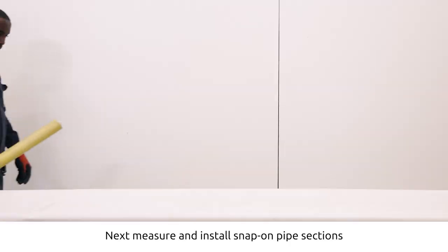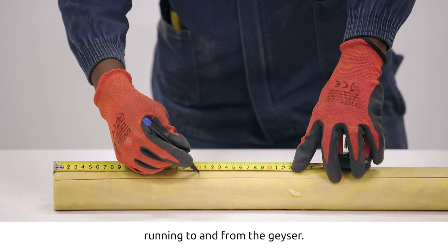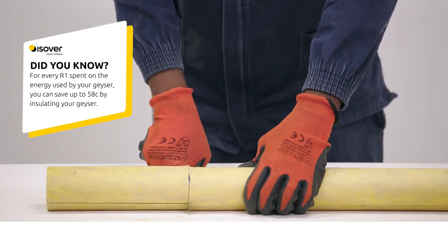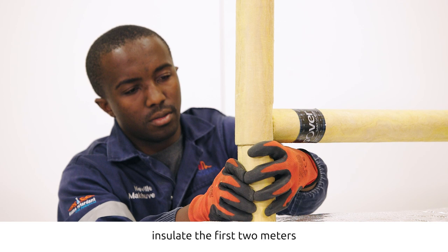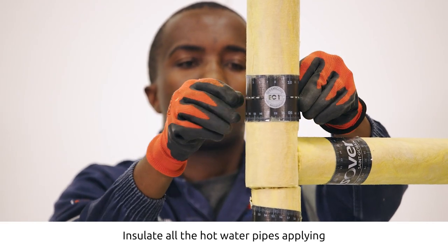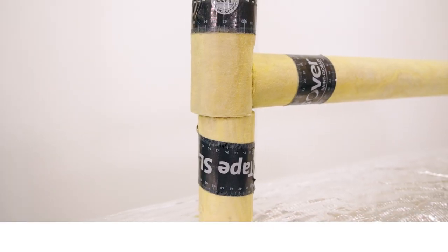Next, measure and install snap-on pipe sections around the pipes running to and from the geyser. From the geyser inlet, insulate the first two meters of the cold water pipe, and insulate all the hot water pipes, applying tape around all the joints. For more information about this product, go to www.isover.co.za.